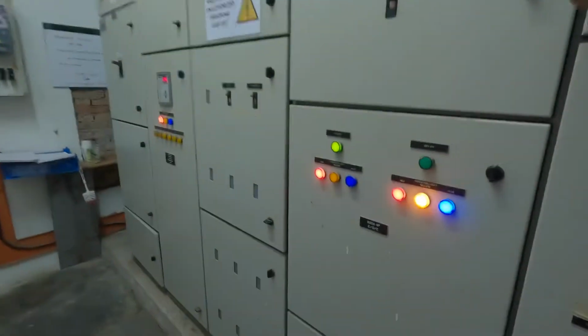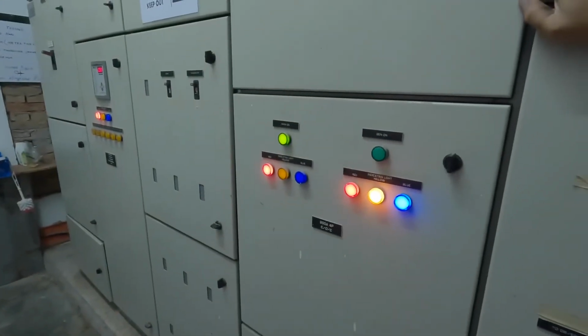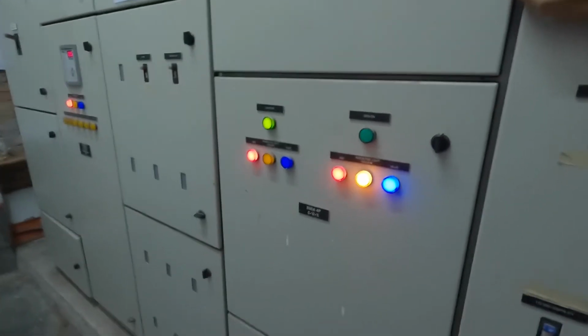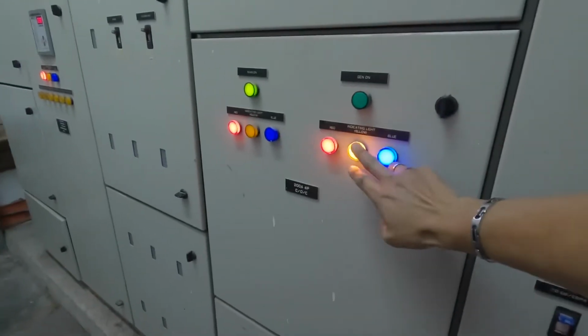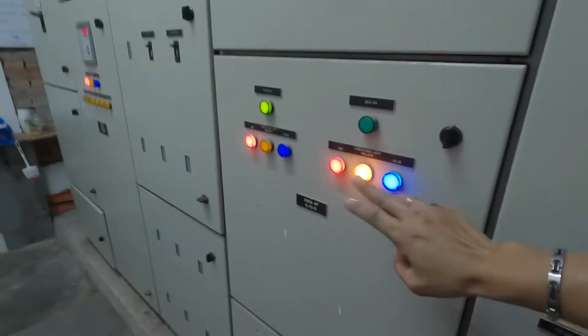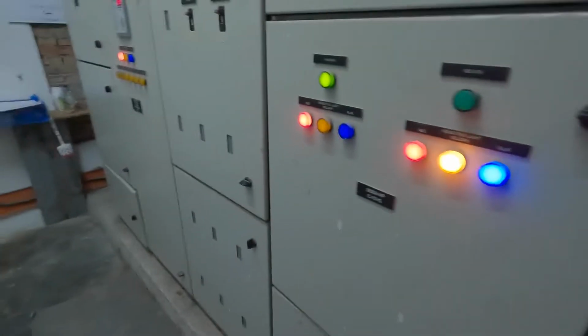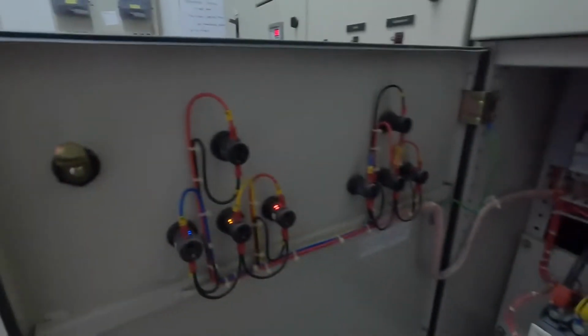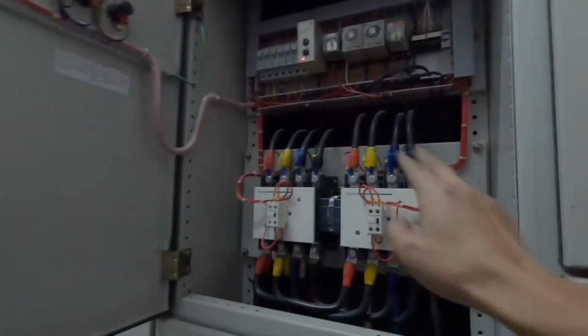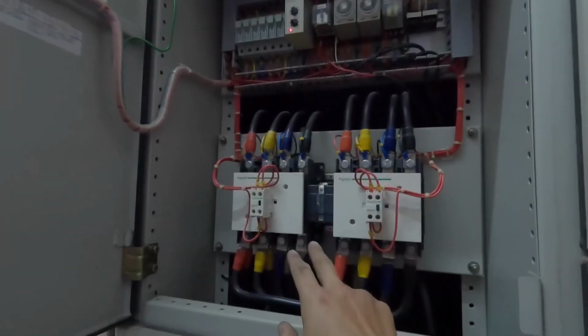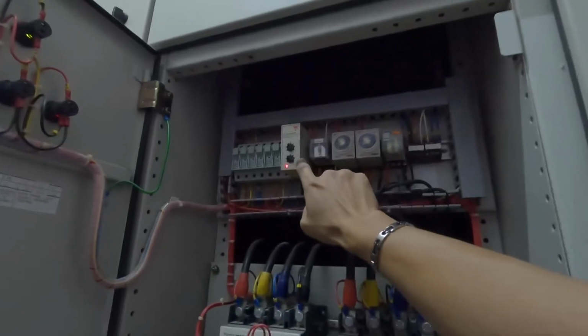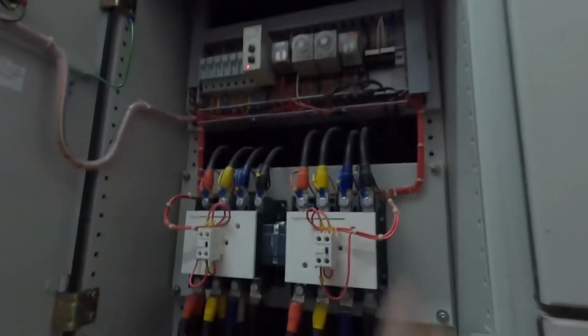Okay, right now we have already switched back on the MCCB from the genset to the ATS. Now the power supply comes here once we on the genset. So this confirms the cable from the genset to the ATS is okay, can be used, no problem. Don't know what the reason was that they off it previously. Okay, right now, once the power supply here is available, it can change over anytime if anything triggers this UVR relay. So we double confirm the power supply is in good condition.